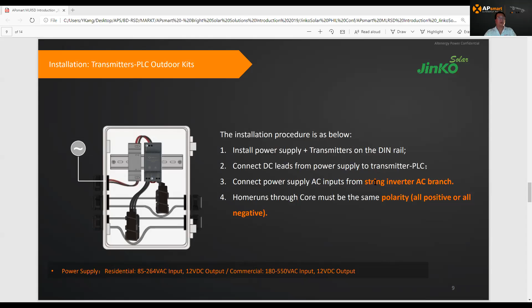Also, when you connect with your wiring, you need polarity, which means all positive must go through this CT, or all negative go through this one. You don't want to mix them, a positive and a negative, because the signal will be messed up. We also have two types of the power supply for the transmitter. One is for 85 to 264 volt. Another one is for 180 to 550 volt. That's for single phase and three phase applications.